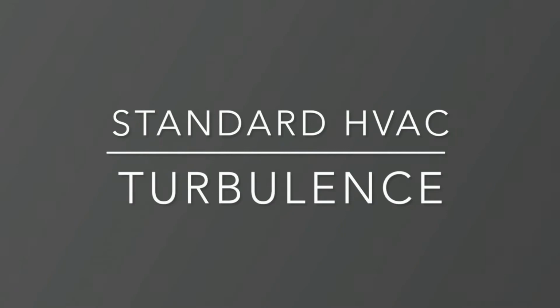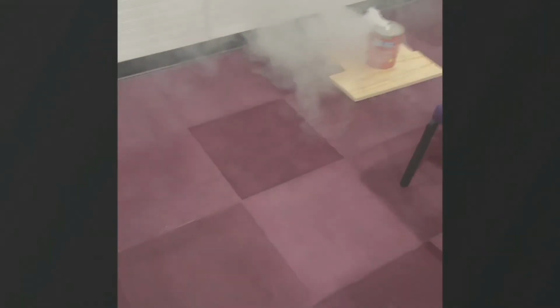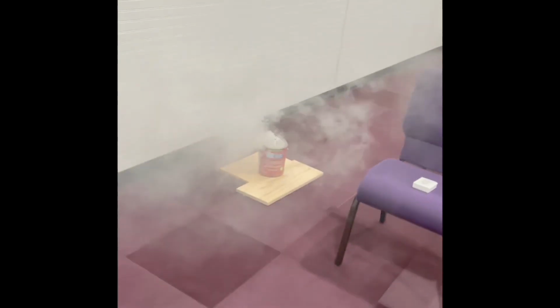This is the video that shows you can put a HEPA filter in this room and it won't help you much with preventing the spread of disease. As you add additional HEPA filters in the room, the only thing you do is make it noisier, because a HEPA filter running at about 500 cubic feet per minute is going to be putting out somewhere in the neighborhood of 70 to 75 decibels. You won't be able to use the room with a lot of HEPA filters in it because you won't be able to hear, you won't be able to talk. You have to talk over those filters.